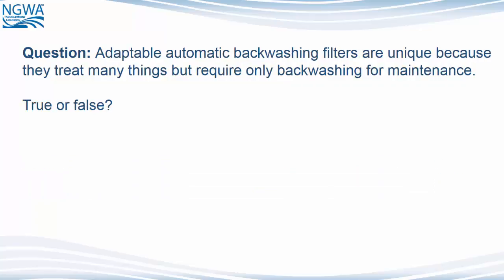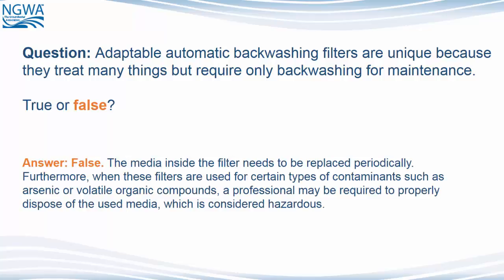Question: Adaptable automatic backwashing filters are unique because they treat many things but require only backwashing for maintenance. True or false? The answer is false. The media inside the filter needs to be replaced periodically. Furthermore, when these filters are used for certain types of contaminants such as arsenic or volatile organic compounds, a professional may be required to properly dispose of the used media, which is considered hazardous.